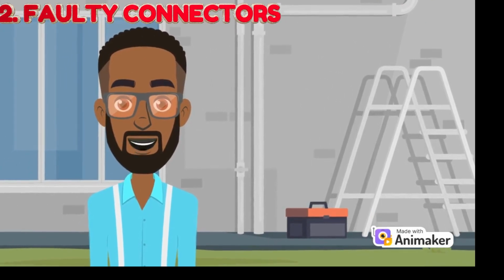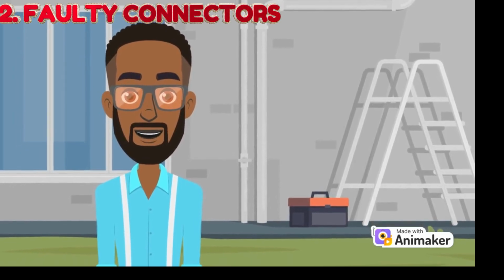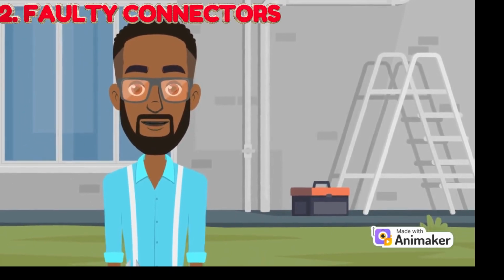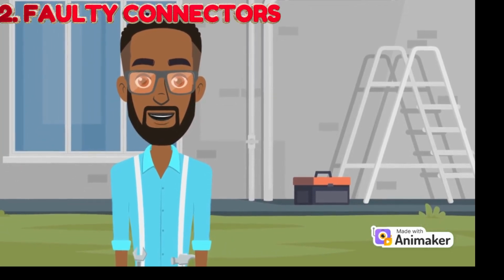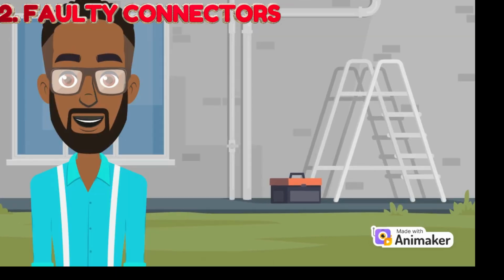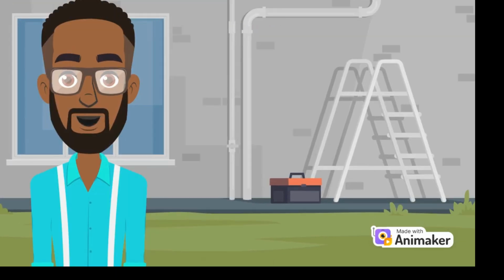2. Faulty connectors. Sometimes due to weather and environmental conditions, rust and dust, bad contact or short circuit, etc. may cause a connector to be faulty. The solution to this problem is to replace the faulty connectors. In some cases, just cleaning and refixing will be okay. After replacing it, ensure it is properly protected by proper insulation and place it in a junction box.